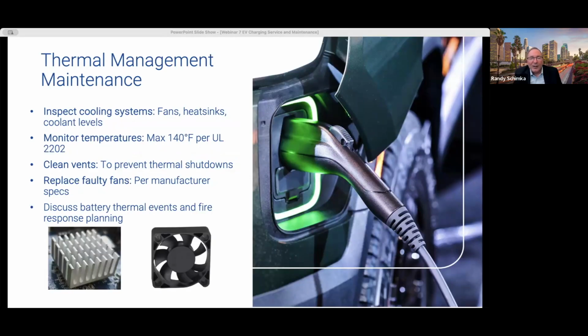Thermal maintenance management helps to keep EV chargers cool and operational. Start with inspecting the cooling systems. Check the fans and the coolant levels regularly. Make sure that heat sinks that are attached to hot running components are free of dust and dirt in the fins and have good airflow to dissipate the heat. Ensure that fans can spin freely and that coolant is topped off to prevent overheating.